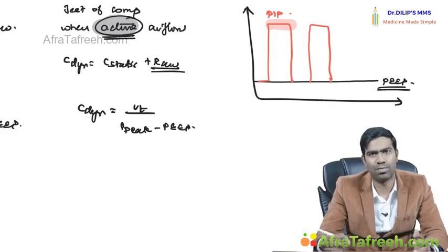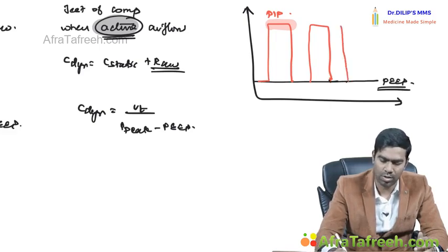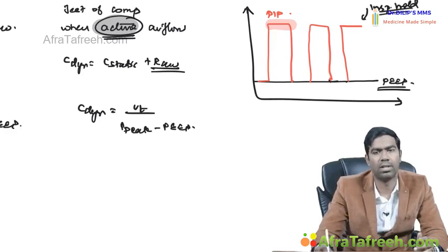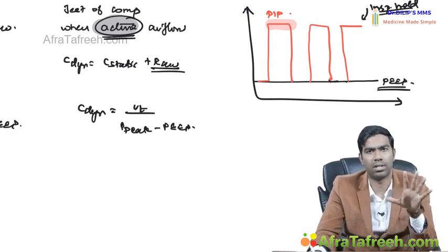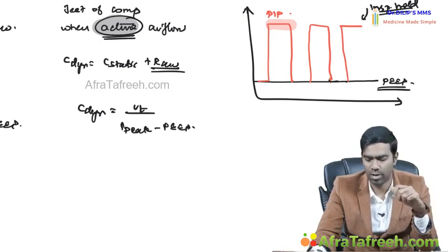And how will you test for the plateau pressure and all these things is by doing something called an inspiratory hold. So let us assume I'm doing an inspiratory hold maneuver. The button is there, you press it, which means after the inspiration, the ventilator will just stop the flow. Nothing will happen. They will just hold and stop the flow, and that's what we call inspiratory hold.